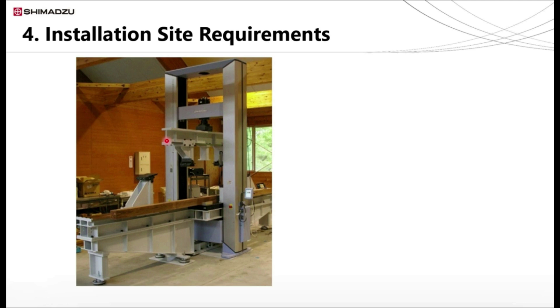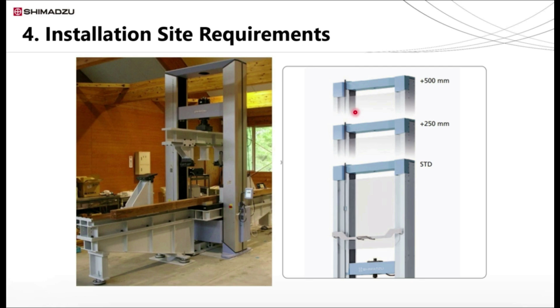Height of the machine is also important. Sometimes samples like flexible plastics, rubber, etc. need an extra height machine as the elongation of such materials is more, sometimes 1400 percent, 1500 percent elongations. So in such cases, select the extra frame length.